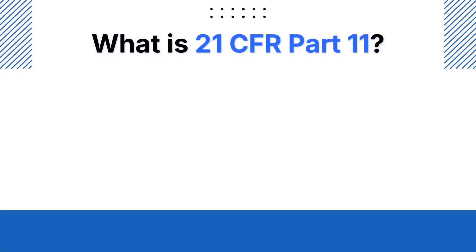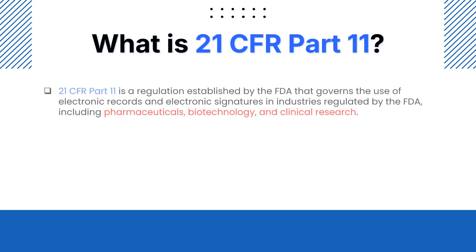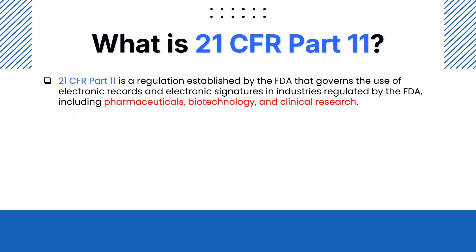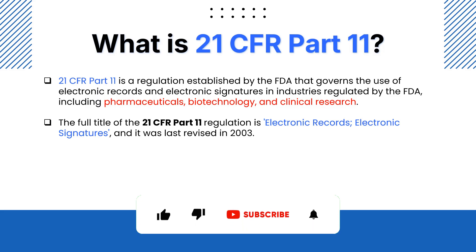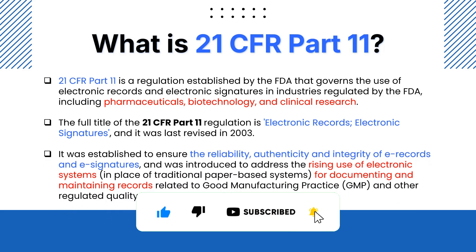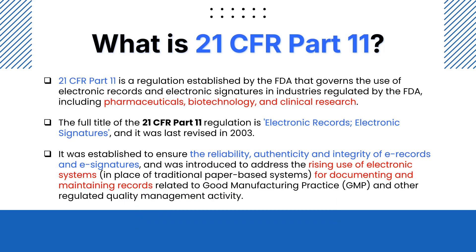So what exactly is 21 CFR Part 11? It is a regulation established by US FDA that governs the use of electronic records and electronic signatures in regulated industries, which includes the pharmaceutical, biotechnology, and clinical research industry. The full title of 21 CFR Part 11 under the regulation is 'Electronic Records and Electronic Signatures,' and the last revision to these guidelines was in 2003. This guideline was established to ensure reliability, authenticity, and integrity in electronic records as well as electronic signatures.